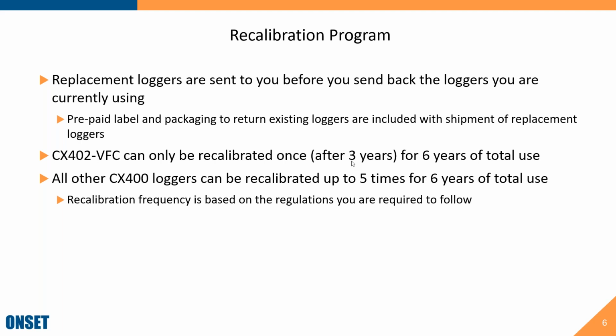Just a quick note on the different loggers here. The CX402 VFC logger can only be recalibrated once. All 400 loggers are good for up to 6 years. And since the VFC logger has a 3-year NIST certificate, it can only be recalibrated once before you have to buy a new logger. All other CX400 loggers can be recalibrated up to 5 times. So again, 6 years of use, so you can do it 5 times because it's a 1-year calibration certificate.